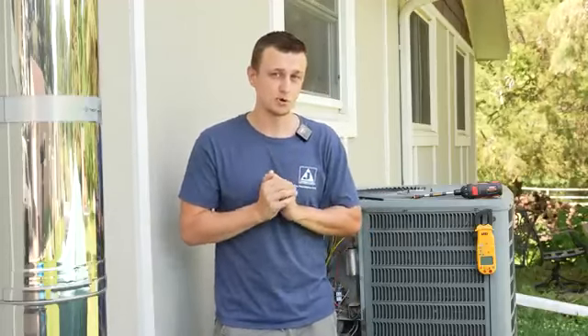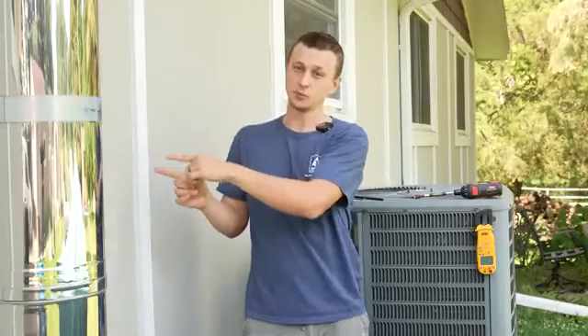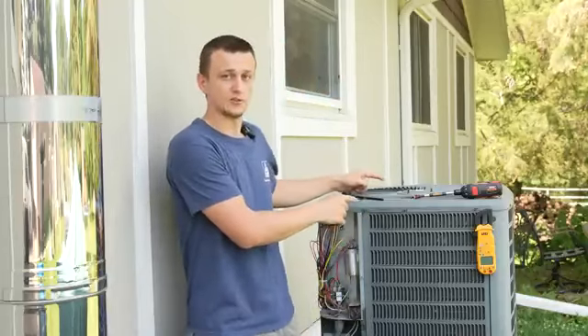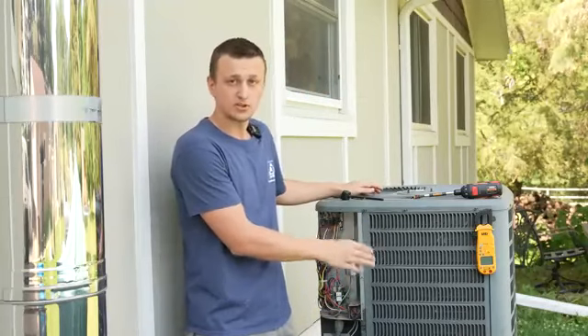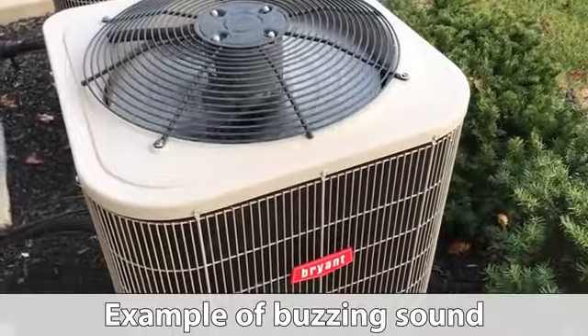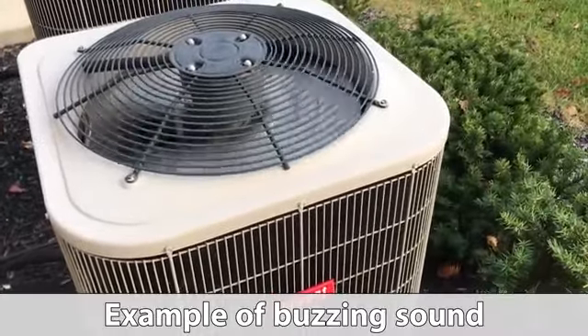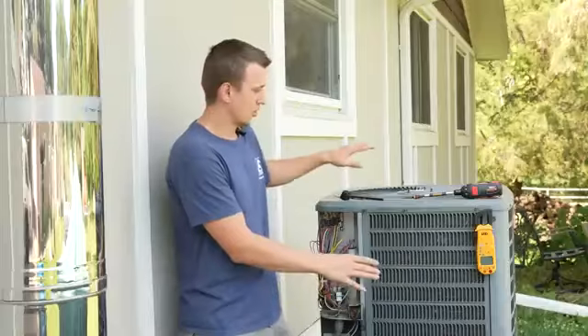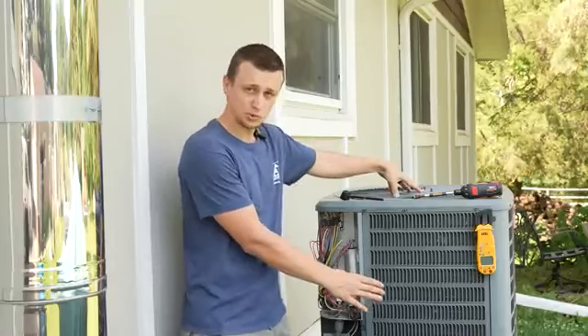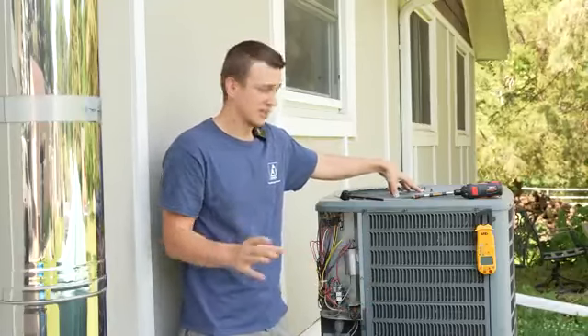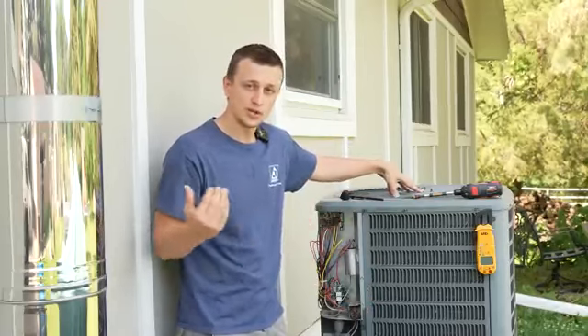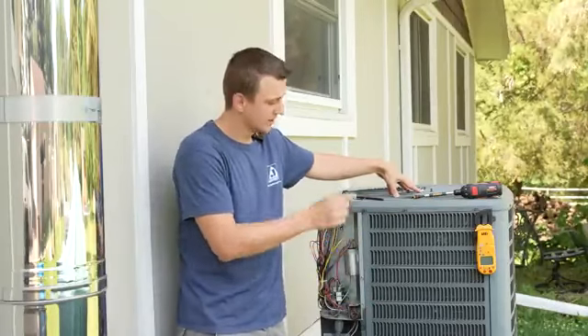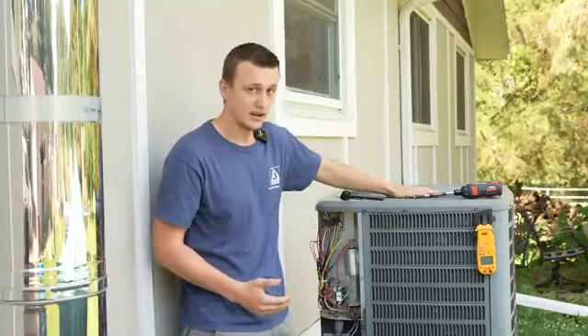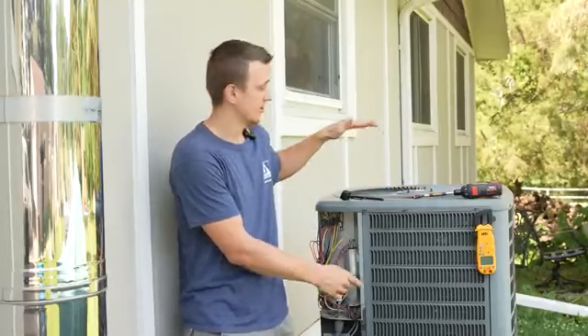Another one, which is a little bit more tricky, is when the fan inside is working, and even the fan outside is working, but the compressor is not working. So when the fan runs and the compressor runs, they make a little bit of a different noise. The fan just sounds like a car window open, just air blowing. But the compressor makes more of a rumbling sound. So usually you should be able to hear the difference if it's just the fan on or if they're both on, the compressor and the fan.